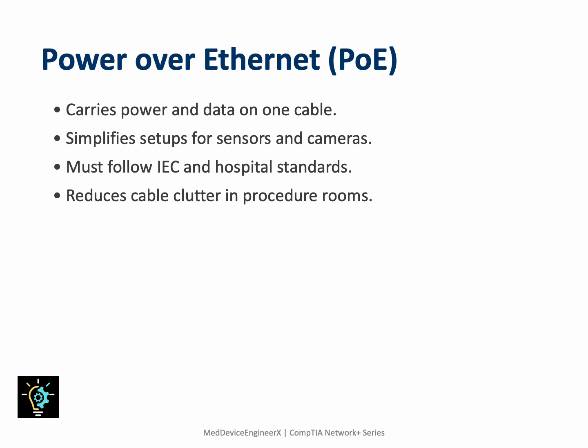Power over Ethernet simplifies hospital installations by delivering both data and low voltage power through a single Ethernet cable. While most medical systems aren't directly powered via Power over Ethernet, it's used for cameras and patient room monitors. Biomedical engineers must ensure electrical isolation and grounding standards are met to prevent hazards.